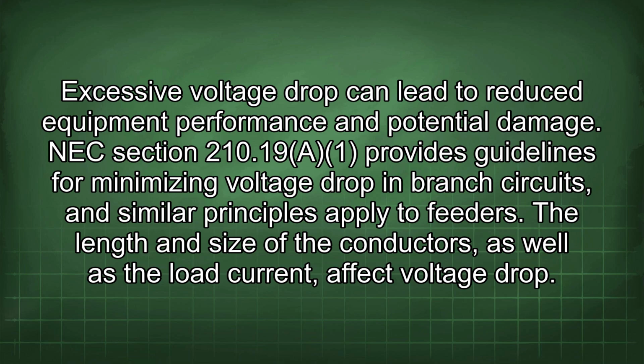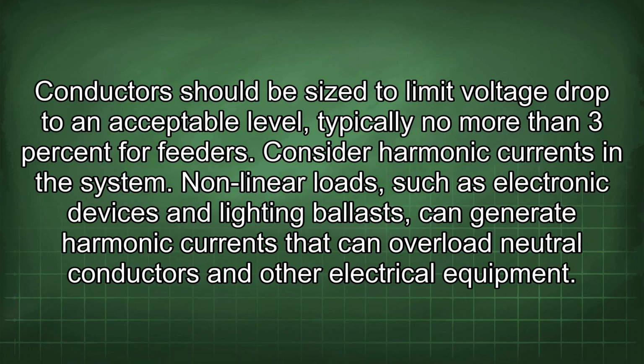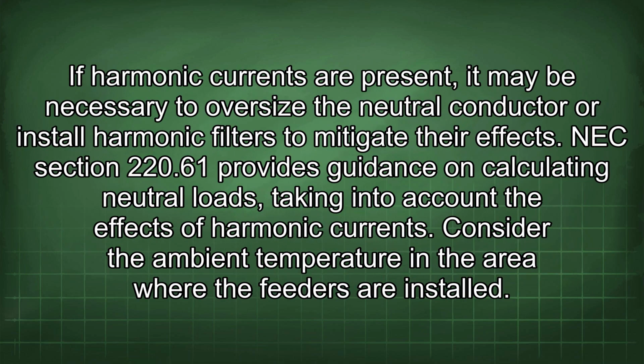The length and size of the conductors, as well as the load current, affect voltage drop. Conductors should be sized to limit voltage drop to an acceptable level, typically no more than 3% for feeders. Consider harmonic currents in the system. Nonlinear loads, such as electronic devices and lighting ballasts, can generate harmonic currents that can overload neutral conductors and other electrical equipment. If harmonic currents are present, it may be necessary to oversize the neutral conductor or install harmonic filters to mitigate their effects.